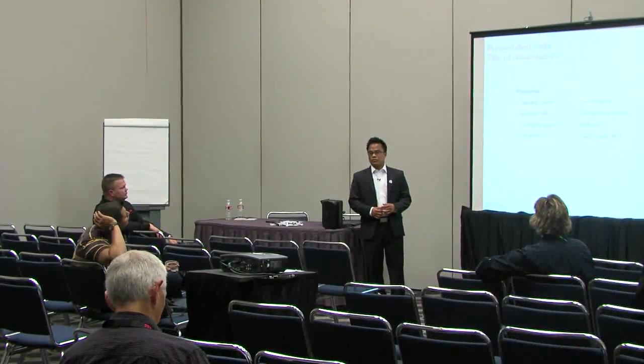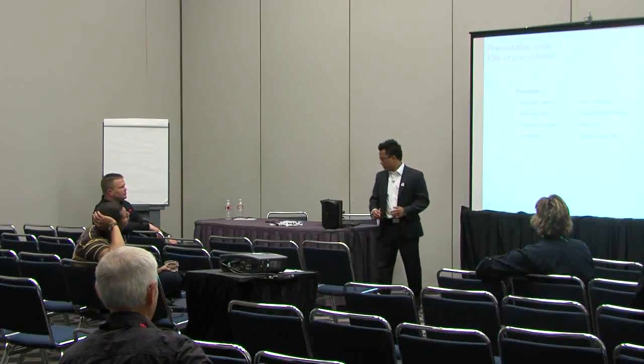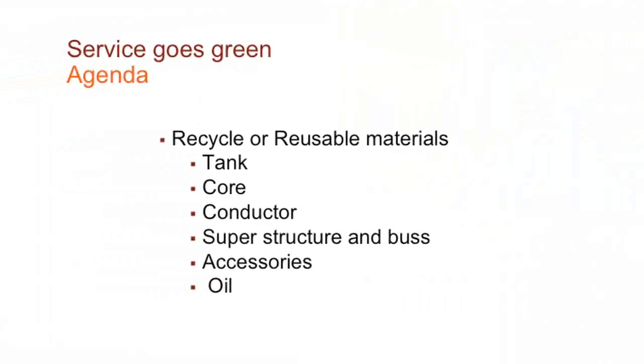So when we talk about transformers, there's several parts of the transformers that we can reuse when we do decide to repair the transformers. The first item that is typically reused in a remanufacturing is the tank. When the tank comes in, we would detank the active part and clean off the tank. Our team has the ability to dry blast the transformer, clean it all up, and repaint and sandblast it as well.